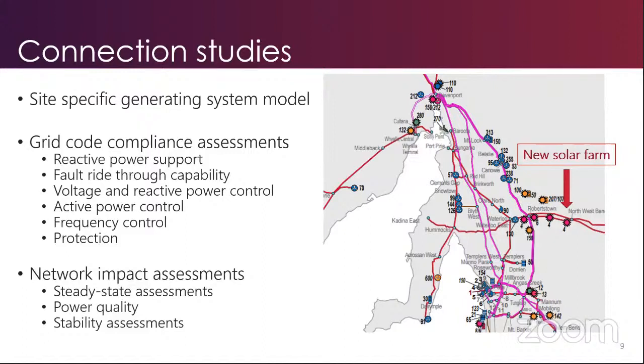This covers things like reactive power support, voltage ride-through requirements, active power control, frequency control, and sometimes protection validation. That's grid compliance. There can be overlap between these two areas, but I try to keep them separate. The next part of these connection studies is to understand the impact this particular generator might have on the existing system.